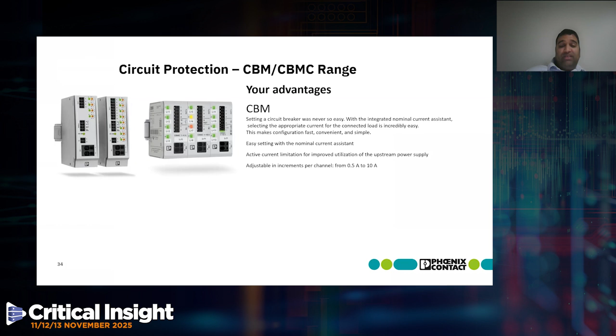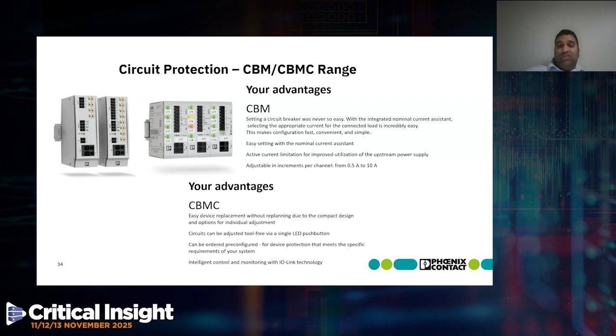It's also intelligent, allowing you to send signals and control back to a control system, like our controller, using IO-Link technology. These systems have IO-Link connectivity so that if a circuit breaker trips, it allows the control system to send an alarm or typical response. The operator, without even knowing a failure occurred, will be notified through this control system, and can then quickly restore and diagnose the problem.